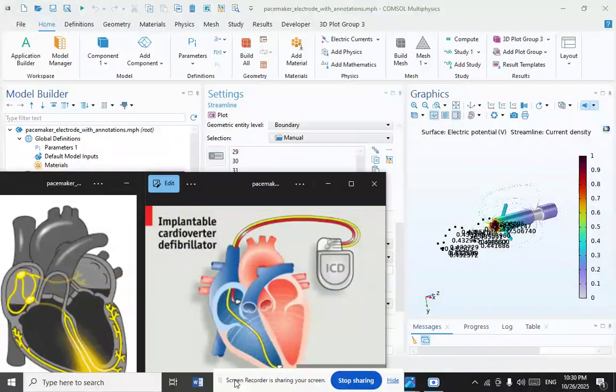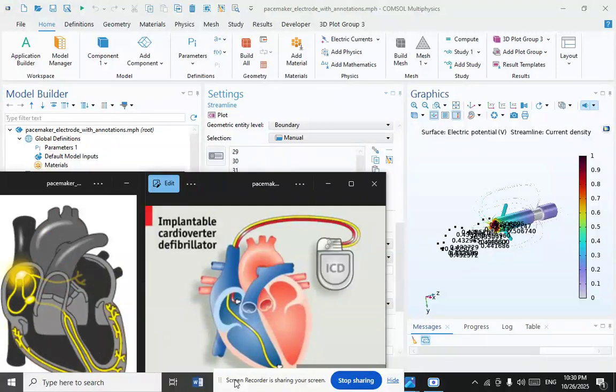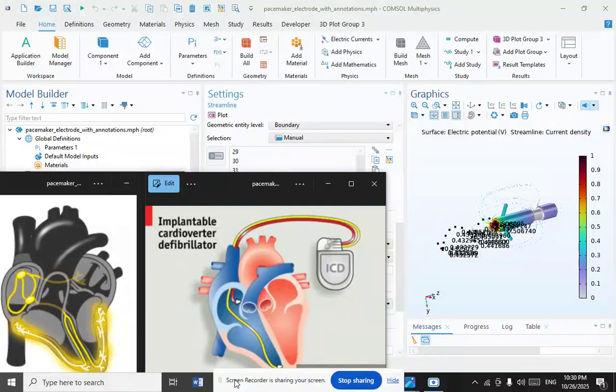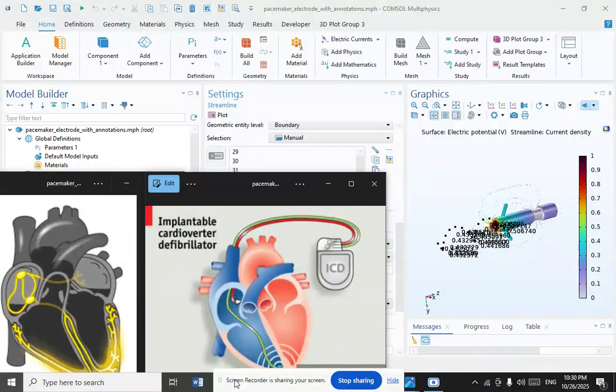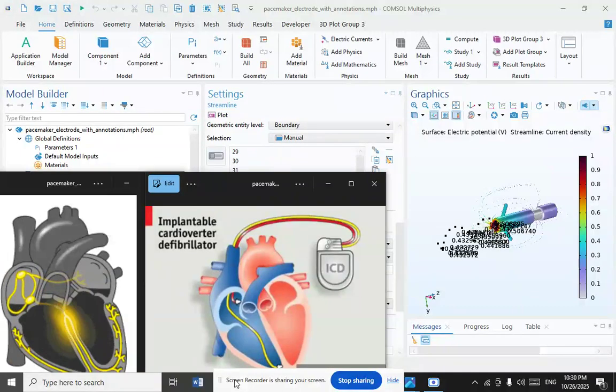And how does it work? The first step is connection. One end of the electrode lead connects to the implanted pacemaker's pulse generator, the battery and circuitry, and at the other end, the electrode is attached to the heart. The next step is delivery. The electrode delivers electrical impulses from the generator to the heart muscle to regulate its contraction. The next one is placement. For a standard system, the leads are threaded through a central vein until their tips are in the correct heart chamber. The next one is attachment. The electrode tip often has a small screw or helix that secures it to the heart tissue.